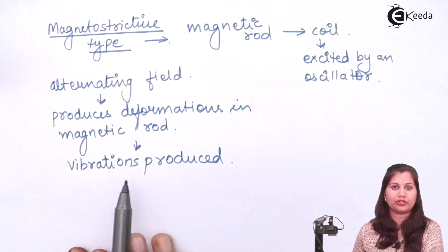In this ultrasonic method, ultrasonic vibrations are produced with the help of a transducer, which converts the electrical energy of an oscillator into ultrasonic vibrations of corresponding frequencies. Different vibrations having different frequencies are generated by the transducers, and the frequency of that vibration is an indication of the thickness of the material.